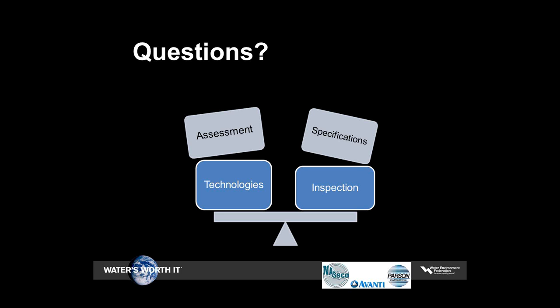The next question is directed to John Manajak: For chimney replacement, what if the groundwater will degrade the butyl between the sections and what measures should be taken? If you're raising the manhole frame and have the area dug out around it, the exterior chimney seal would be a good option — you could put that on after you replace the rings, giving you a full wrap and full protection on the outside. The other option would be to put interior boots on, which will fit nicely in a newly constructed chimney of the same size.